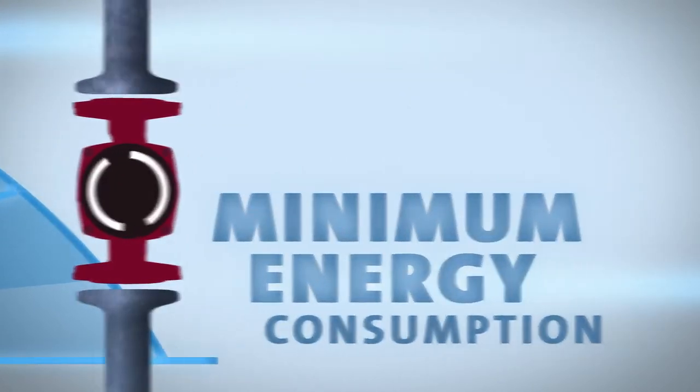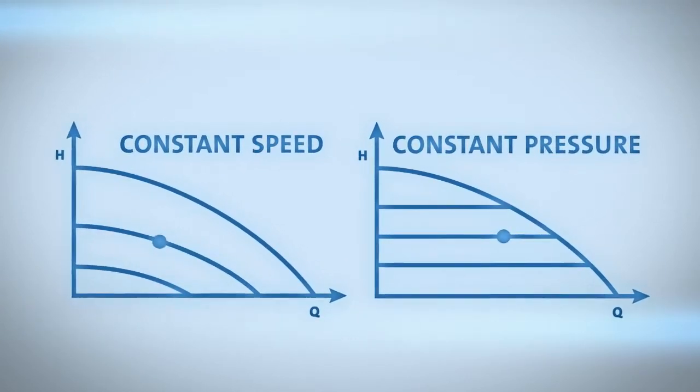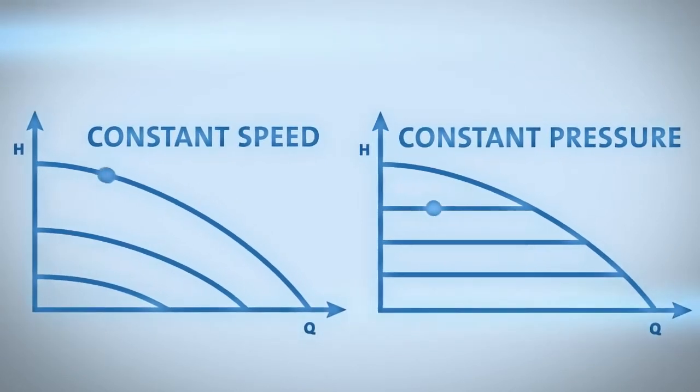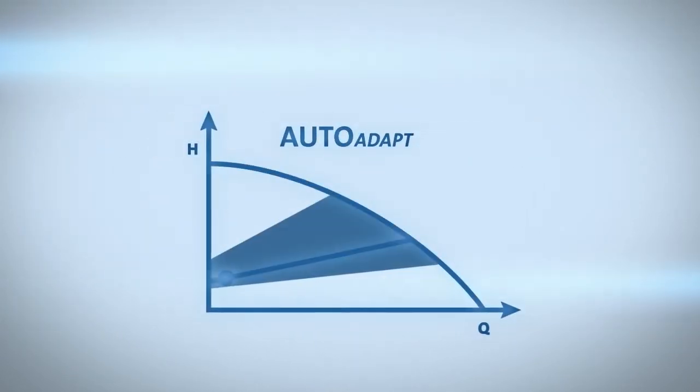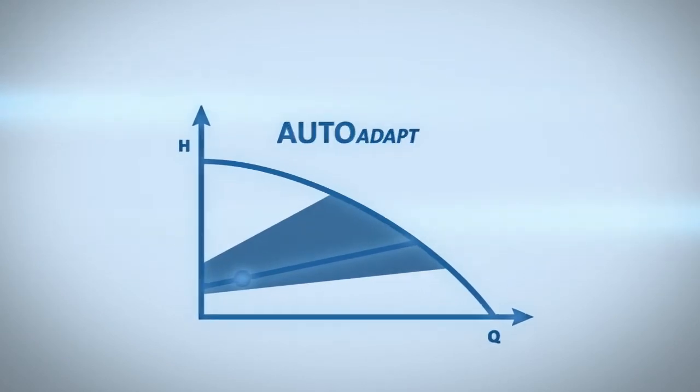Pump and motor combinations have the following hydraulic and electrical relationships. Alpha software monitors amps or the load on the motor. Based on its findings, AutoAdapt automatically adjusts the motor speed to compensate for the new load requirement.